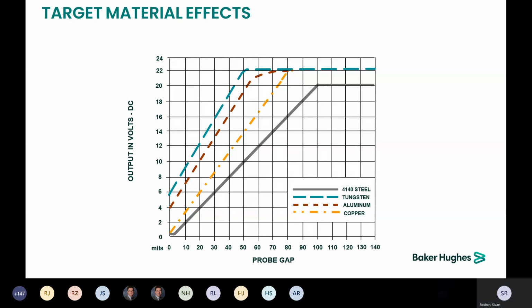So anytime you replace the shaft, make sure that you confirm what the shaft material is and get a proximitor to match. It can throw the signal off a good bit by scale, and in certain alloys, it actually causes kind of an S-type shape to the curve, so it's not even linear. So you can't just say, oh, well, it's 165 millivolts per mil. So making sure that the proximitor is calibrated for the shaft material is very important.